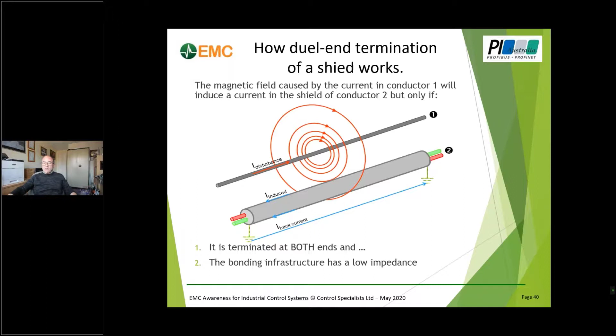The correct terminology is that we should terminate at both ends to a low impedance bonding infrastructure. The fact that the bonding infrastructure is earthed or grounded is a safety point of view - it's got to be fine, carry on doing it, but we're not particularly interested in that from an EMC point of view. What we're interested in is that the voltage of the bonding at one end compared to the other should be relatively low.